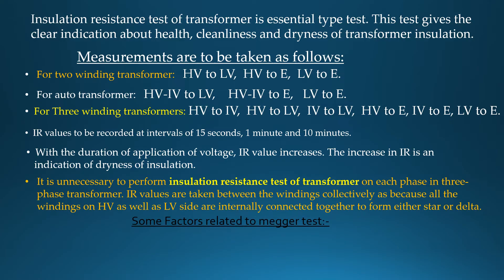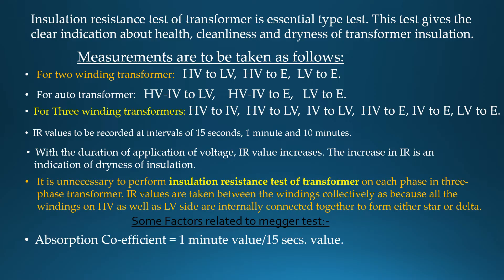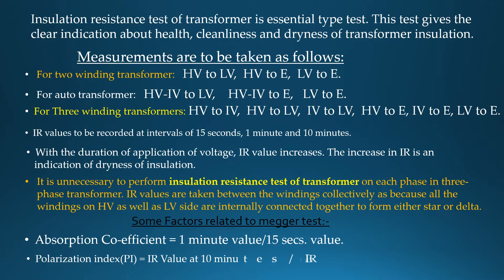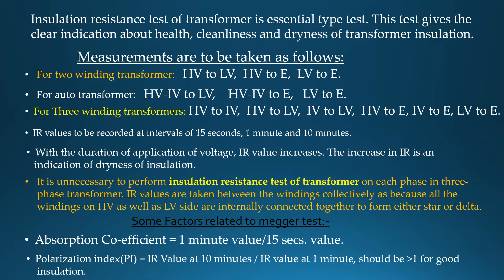Some factors related to the megger test: Absorption coefficient is equal to the 1 minute value divided by the 15 seconds value. Polarization index PI is equal to IR value at 10 minutes divided by IR value at 1 minute, and should be greater than 1 for good insulation.